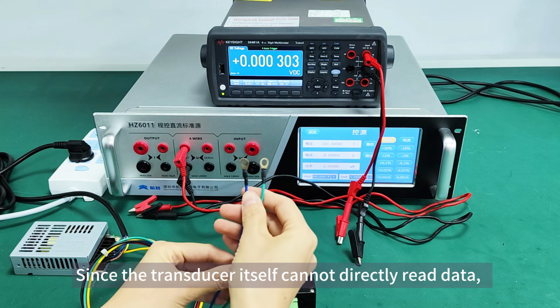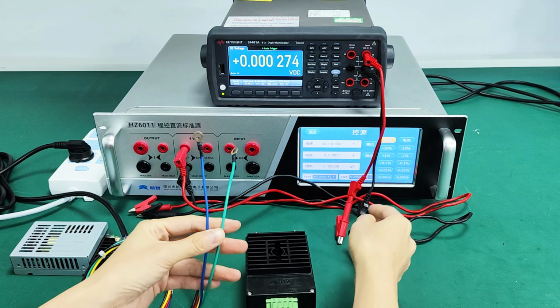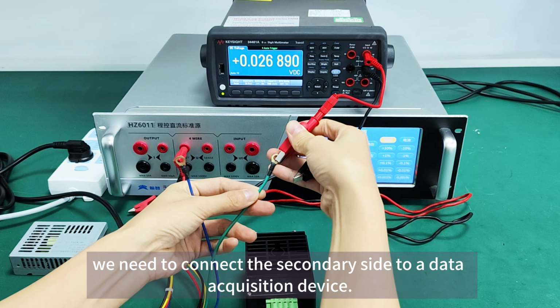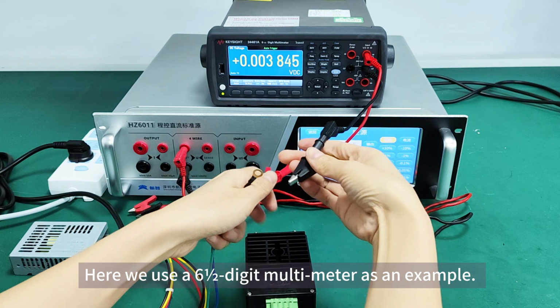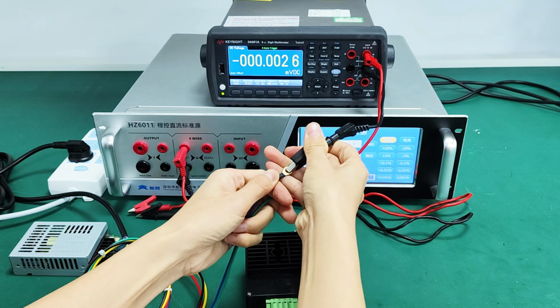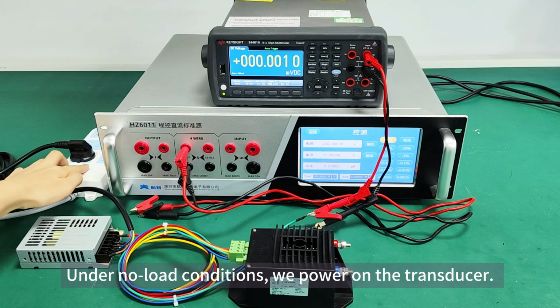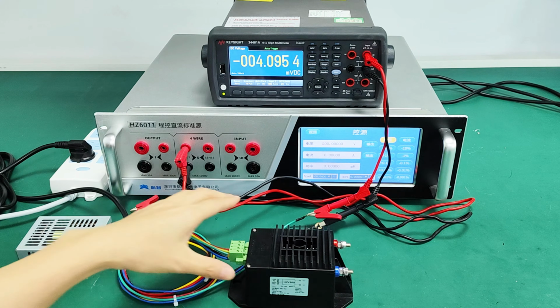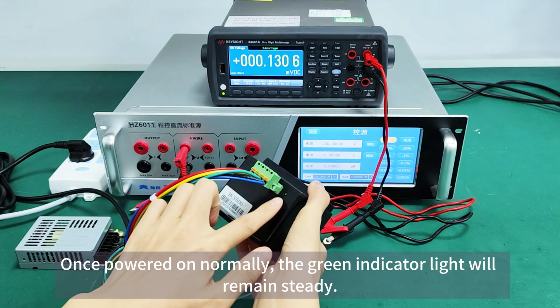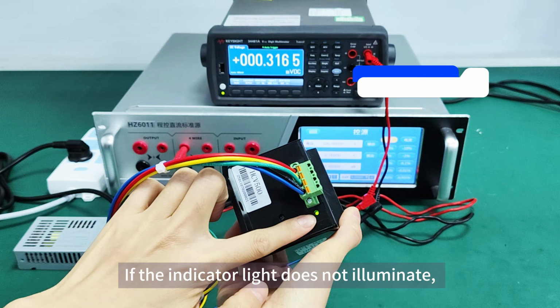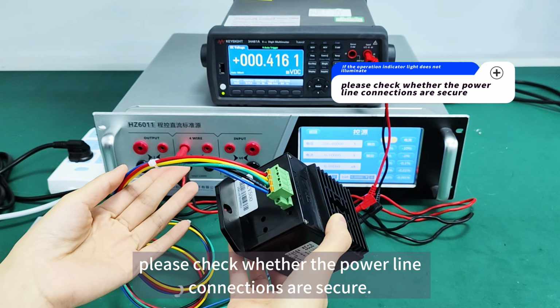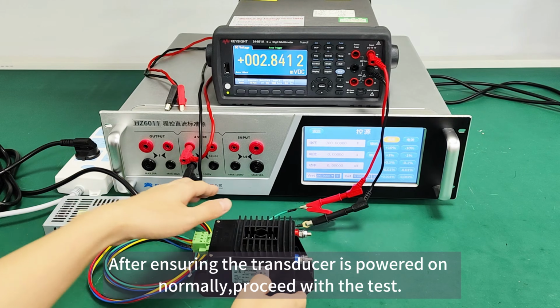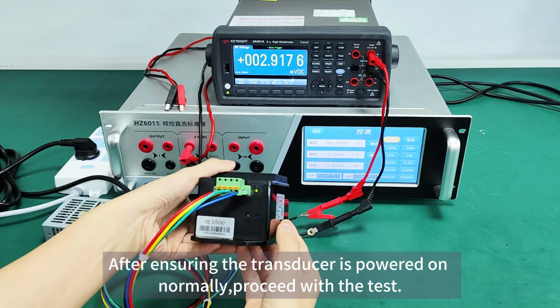Since the transducer itself cannot directly read data, we need to connect the secondary side to a data acquisition device. Here we use a 6-digit multimeter as an example. Under no load conditions, we power on the transducer. Once powered on normally, the green indicator light will remain steady. If the indicator light does not illuminate, please check whether the power line connections are secure. After ensuring the transducer is powered on normally, proceed with the test.